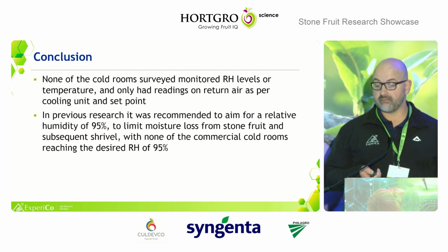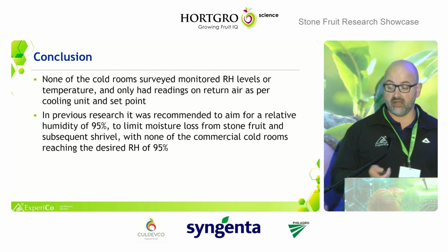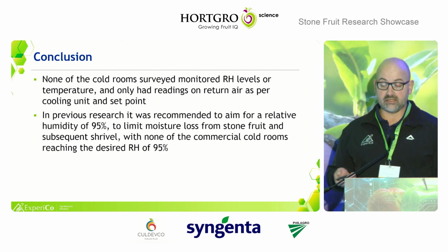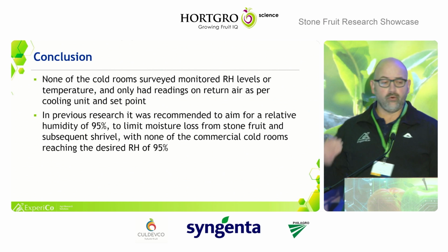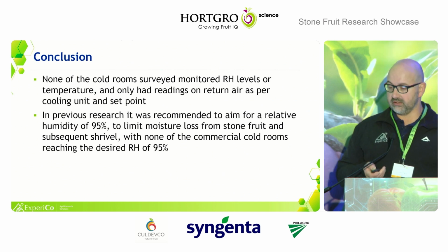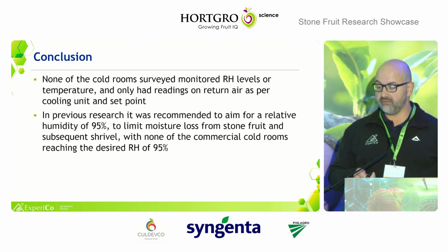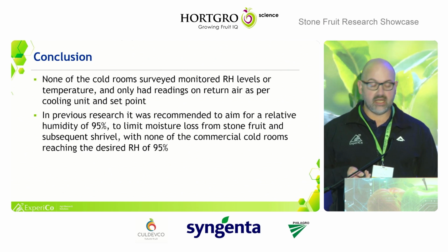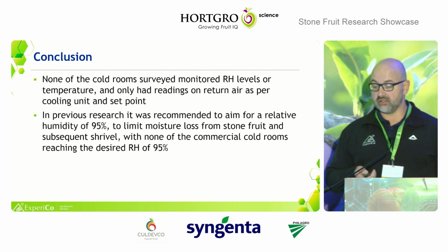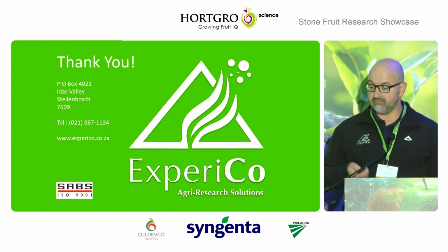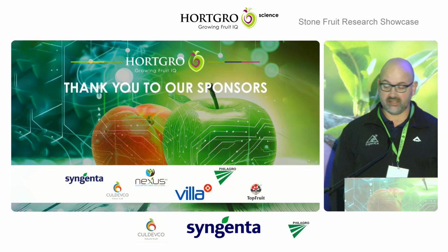In previous research, it was recommended to aim at a relative humidity of above 95%. We see that's obviously difficult in commercial conditions because you've got your door open and forklifts coming in and out, so it's very difficult to manage. But you have to limit the moisture loss in stone fruit, and that will also limit the shrivel levels that you will have after the storage period. And that's my wrap-up for the moisture and the RH in cold rooms.